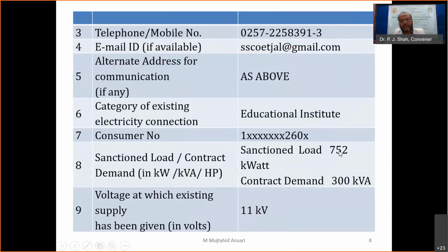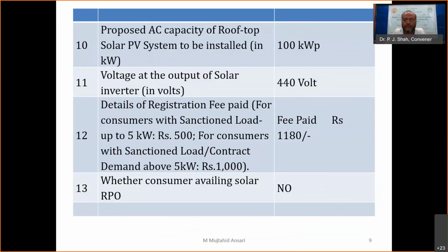So the college presently has a 752 connected load, whereas the contract demand is 300 kVA. When the contract demand is 300 kVA, we cannot connect more than 300 kVA capacity of PV power plants. Either we have to enhance the capacity of the transformer, or we have to go for enhancement of the maximum demand. Once your maximum demand is enhanced with the permission of MSEDCL, then you are entitled to connect a higher capacity power plant to the grid system. So what the voltage level is and what the capacity of the power plant is get included in annexure 2.